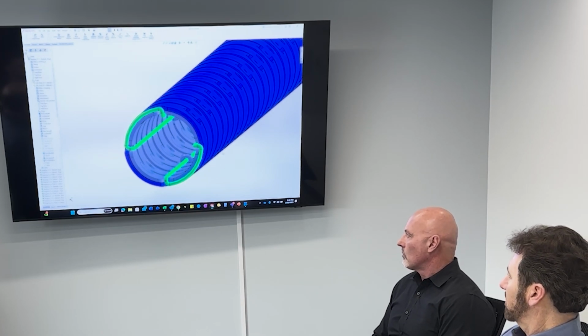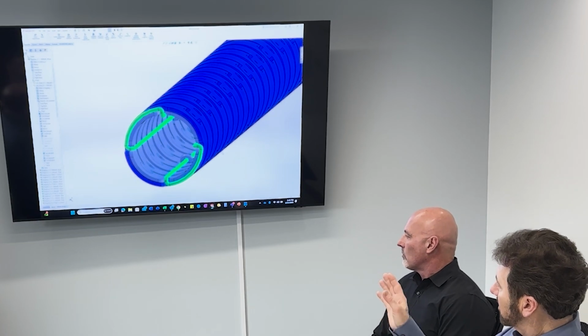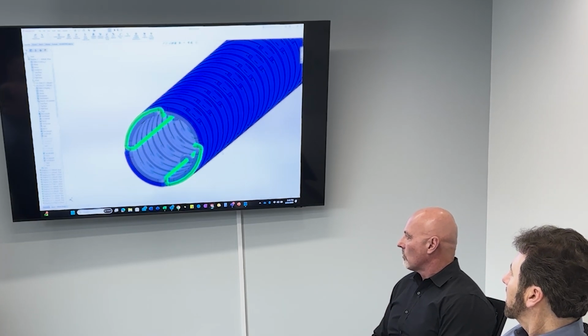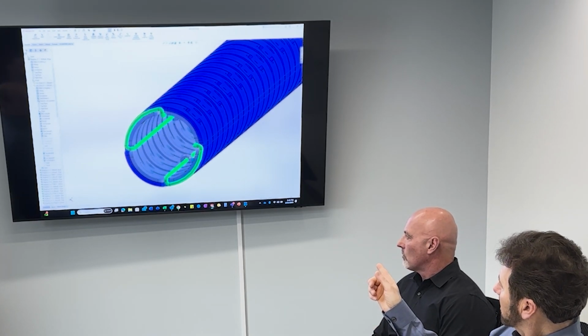There are some features that we're able to put into this, like cable management on the end that we're seeing right now, as well as cable management throughout, where you're seeing the little hoops there. Those are all part of the laser cut hypotube section, and we can take these and assemble them, and just with tacking them together to prevent them from moving around relative to one another. We're able to make this assembly, which is extremely versatile, extremely strong.